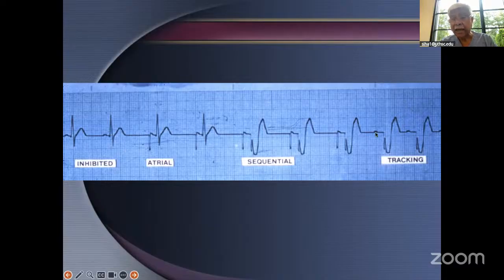And here, A sensed, V paced. That means the sinus node is normal, but it cannot conduct through the AV node. It has to track through the pacing. That's why when it is A sensing, V pacing, it is also called tracking. So these are the 4 different phases of the dual chamber pacing. It could be normal completely. You put the magnet on the pacemaker, they will start firing both. They say, okay, pacemaker is working. A is good, V is not coming up: A-sensed, V-paced, that is also called tracking.